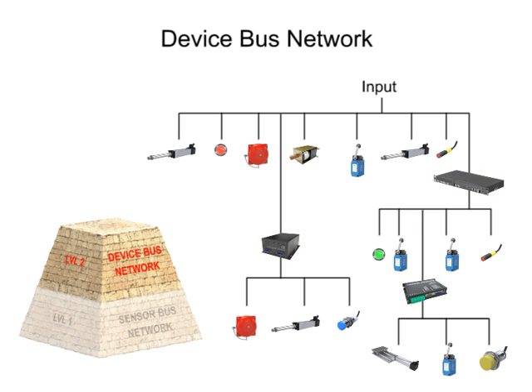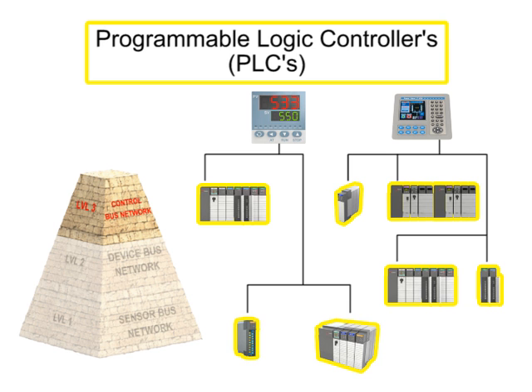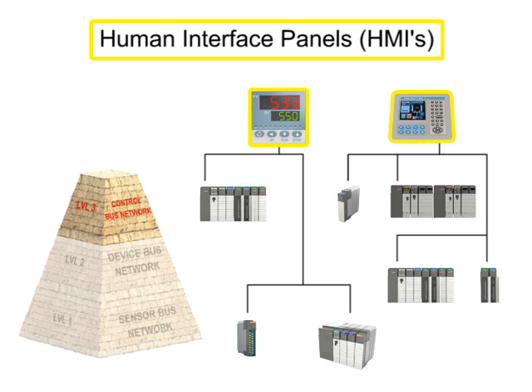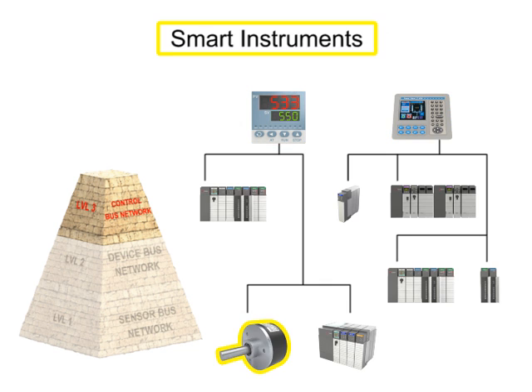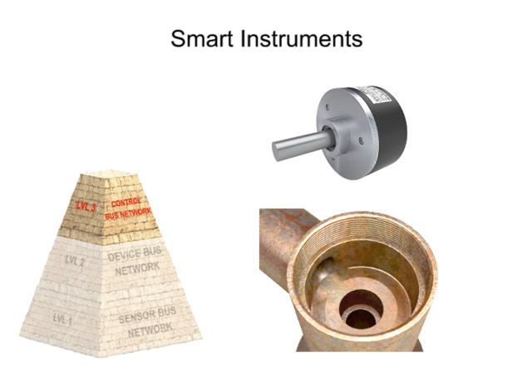Moving up the pyramid, the next increasingly complex level of fieldbus networking is the controlbus network. Controlbus networks are the most advanced networks used on the factory floor and data communication happens at a high level. PLCs or Programmable Logic Controllers are connected to each other alongside HMIs or Human Interface Panels to allow for complete configuration and control of every instrument on the network. Smart instruments capable of performing complex operations can also be connected at this level. For instance, there might be a smart instrument that measures wear and tear on a valve; when the wear reaches a dangerous level, it will signal the controller that the valve needs to be replaced.